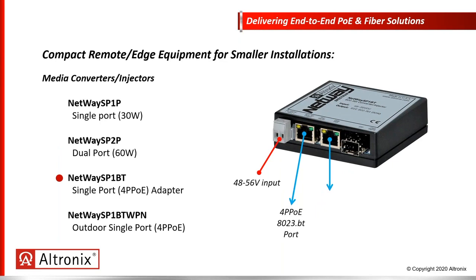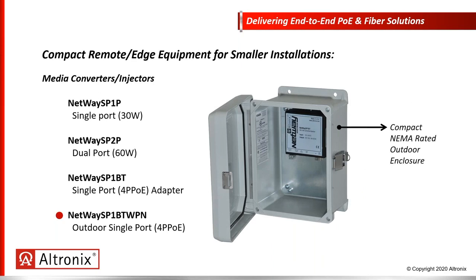Altronix is the first to bring to market compact hardened media converters designed to leverage the new 802.3 BT PoE standard. The 802.3 BT standard was ratified at the end of 2018, and it now allows PDs, power devices, to call for up to 90 watts of power from the power sourcing equipment. It's also known as 4P PoE, standing for 4-pair power over Ethernet, as we're using all 4 pairs inside the Cat6 or higher cable to deliver power, in this case a copper pair to our SP1BT. Having 802.3 BT power and an all-in-one outdoor Nema 4 IP66 enclosure is awesome when we have to design a system with a compatible device.